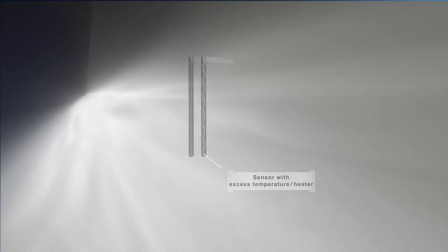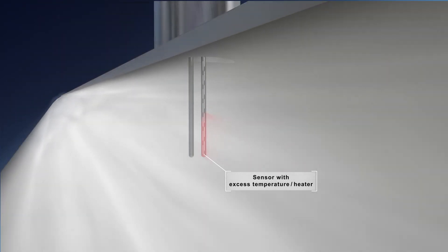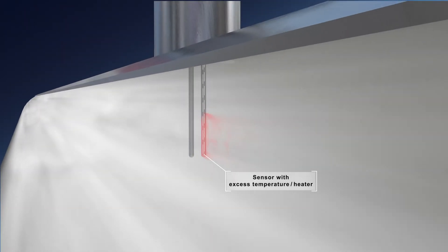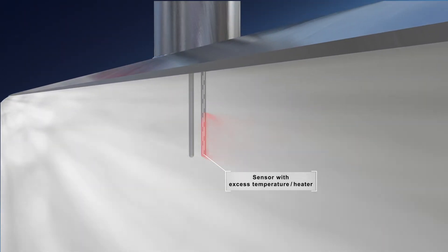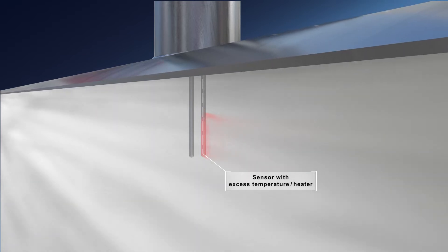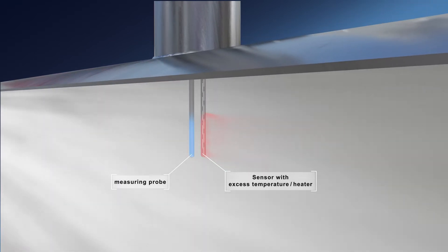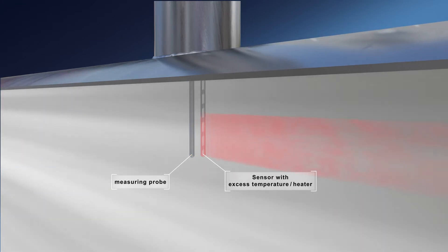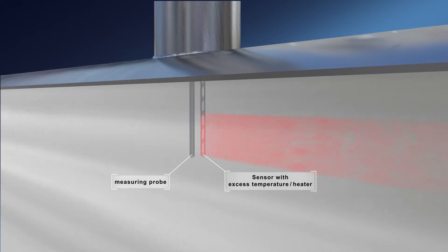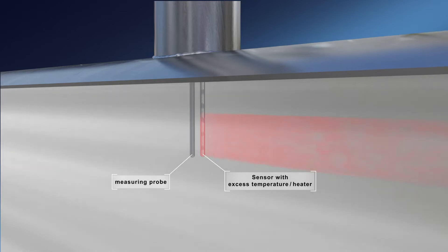With constant temperature anemometry, a part of the sensor works with a towards the ambient temperature constantly held excess temperature. To ensure constant excess temperature, the ambient temperature has to be measured as well. When the flow velocity increases, the current is raised until the heat loss caused by the flow is compensated. The tracked current is therefore a measure for gas mass flow.